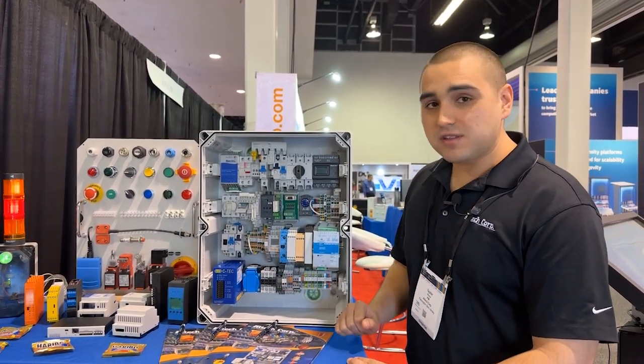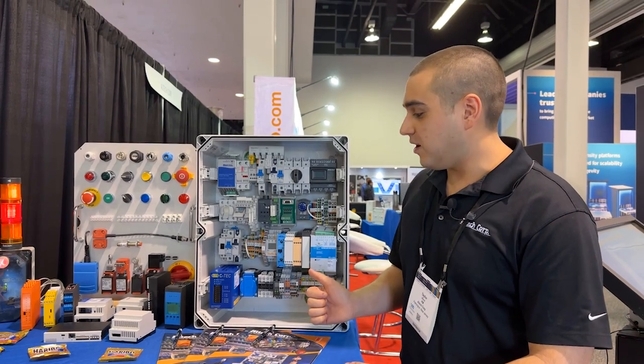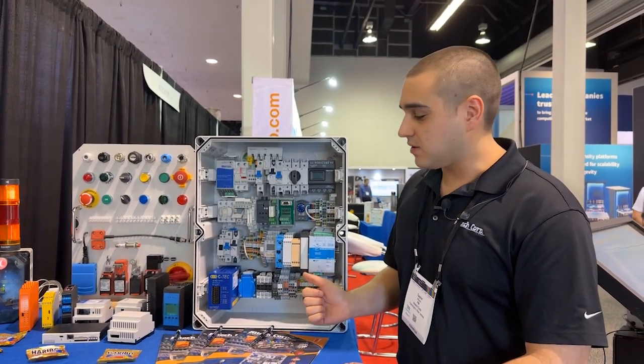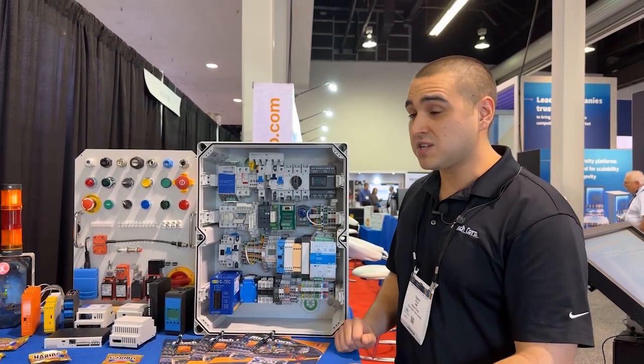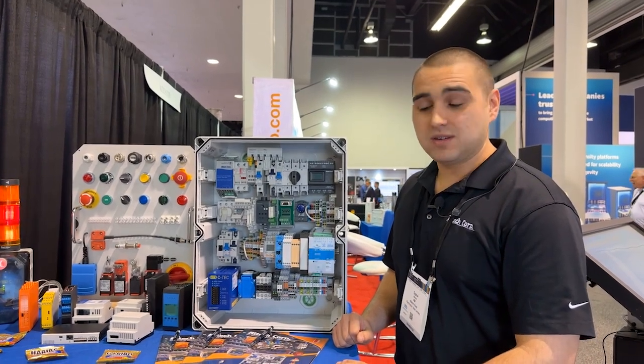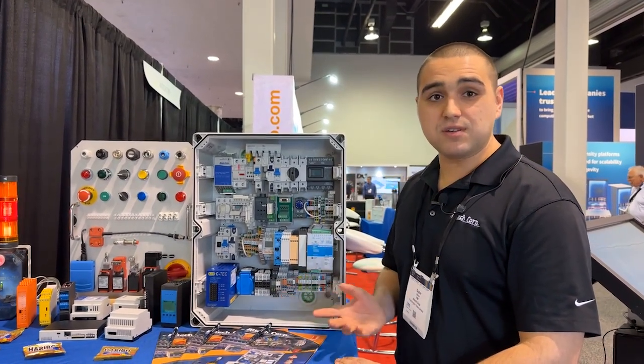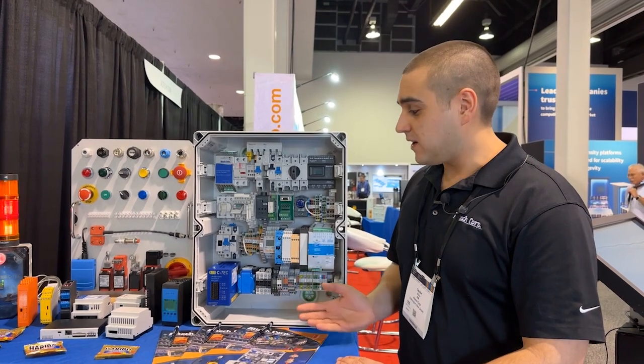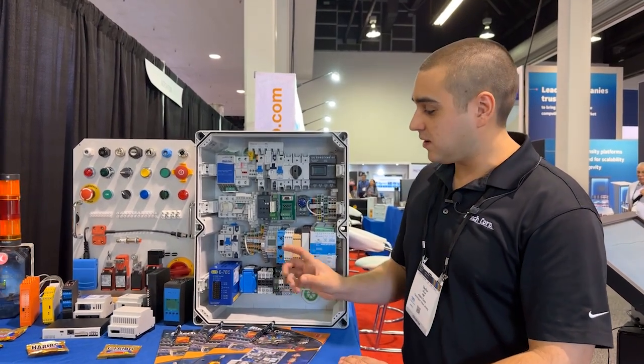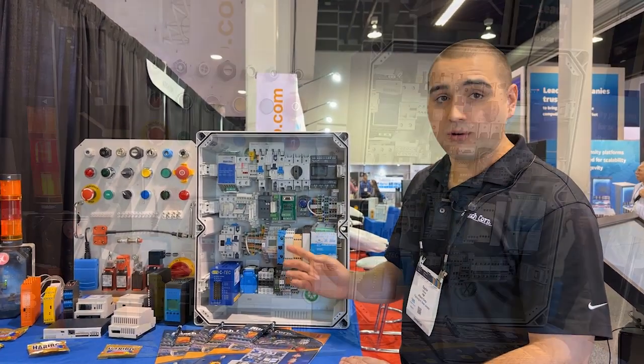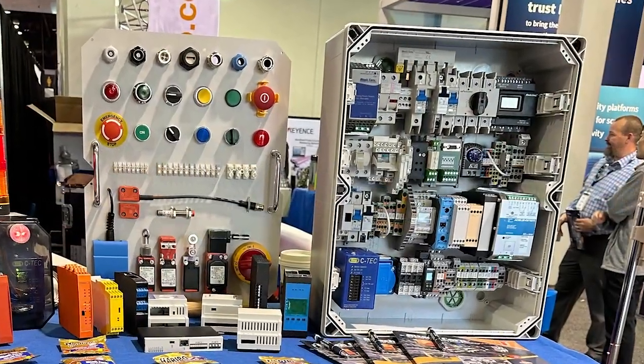The interesting thing about the DC UPS system is that it has a long lifespan, so in optimal conditions it can last up to 20 years, depending on how many cycles you go through of charge and discharge. If you operate in optimal ambient conditions, it'll last quite a long time.